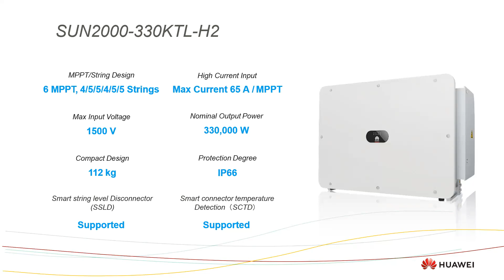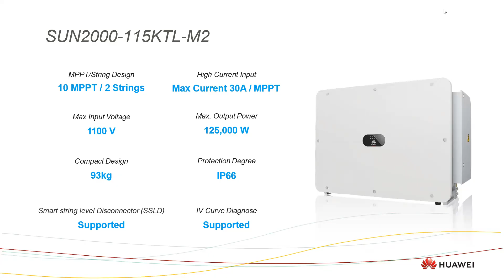This is another inverter for utility scale projects, mostly 500 kilowatt to 1 megawatt, depending on the requirements and conditions from the clients. It has 10 MPPTs, with 2 strings connected to each MPPT. It has 1100 volt DC input, and the same IP66 protection rating, so it can be installed outside. Its output power can be up to 125 kilowatts depending on the environment temperature.